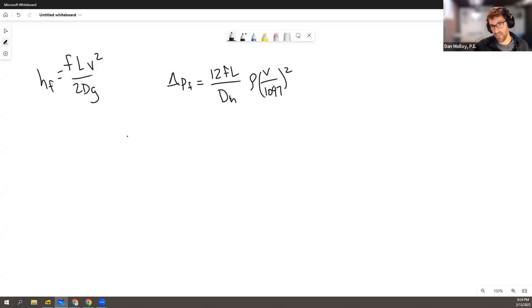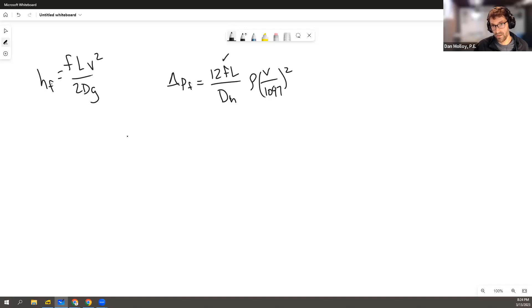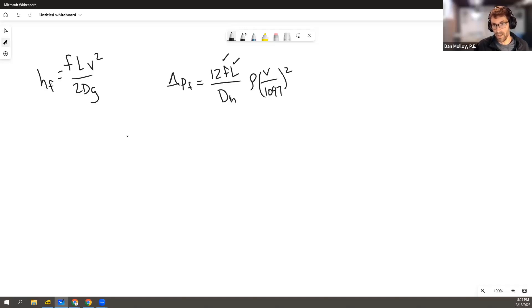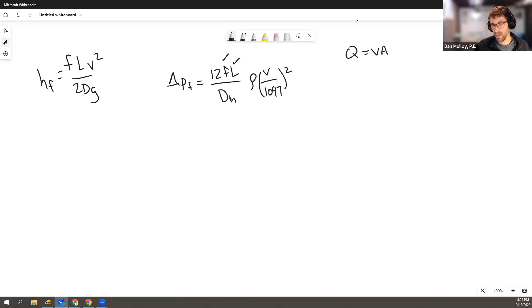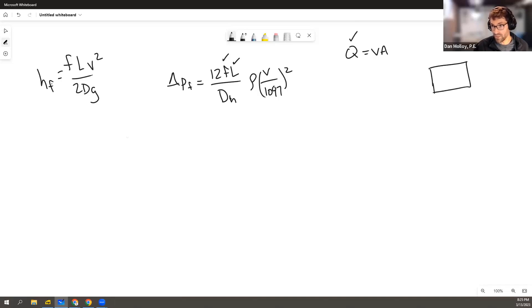And there's some requirements for this. First, F is unitless, and that's given in the problem, so no issue there. And L, we want to know the friction loss per 100 feet, so that's also known. And the velocity, we don't know, but we can find that out from the continuity equation, Q equals VA. We have the volume flow rate. It's a rectangular duct where the dimensions are known, so we can find the exact area of that duct and we can work out the velocity.